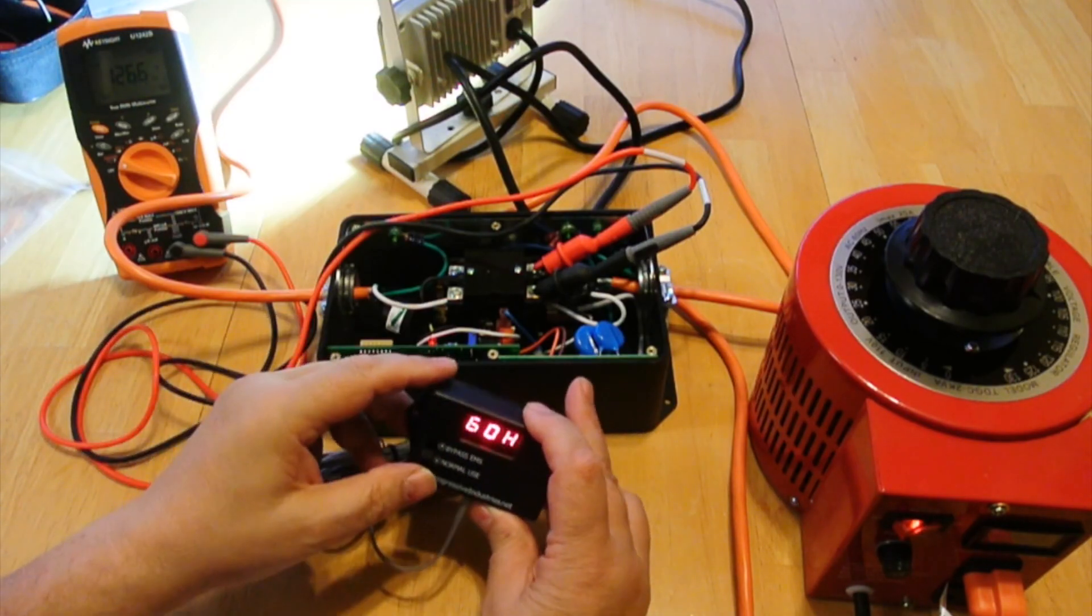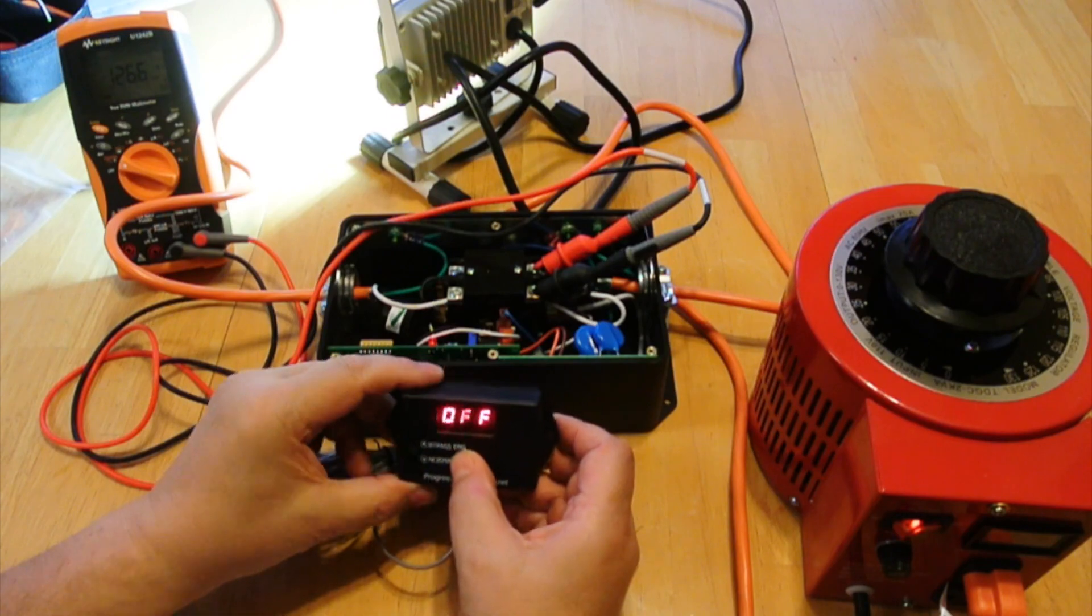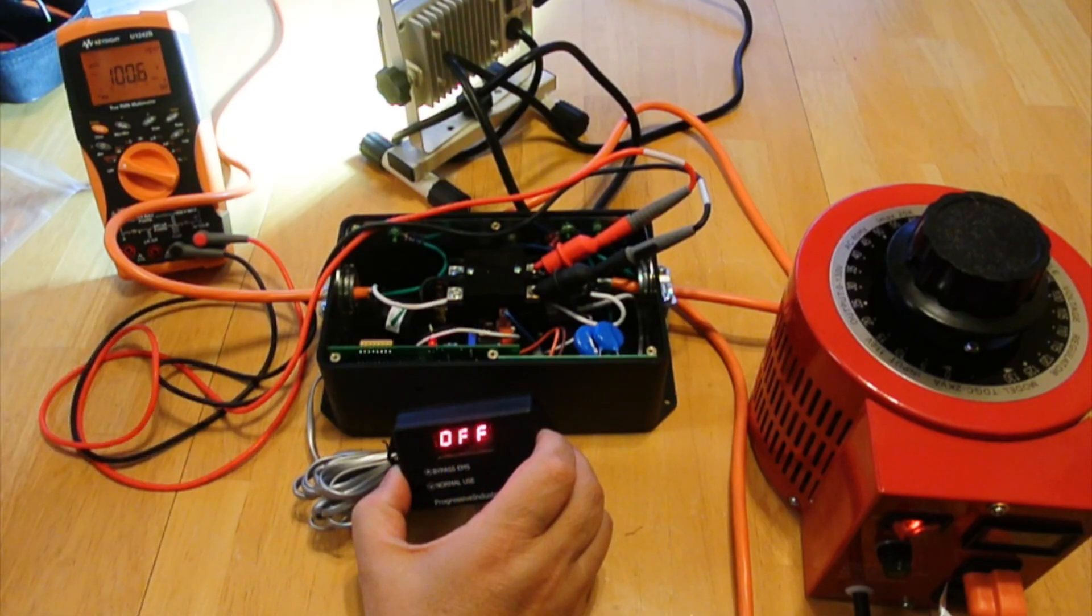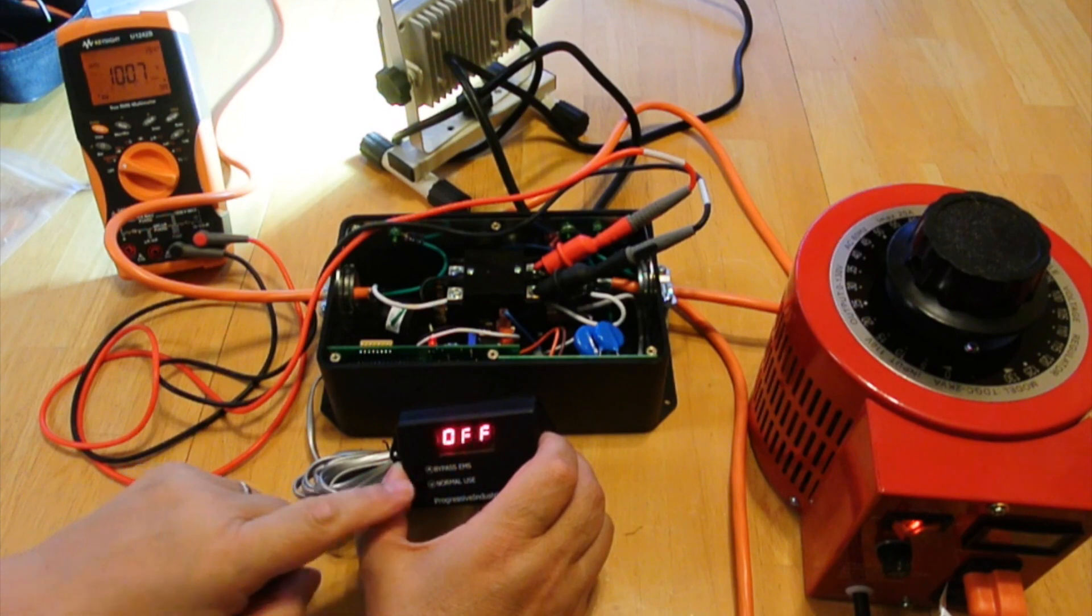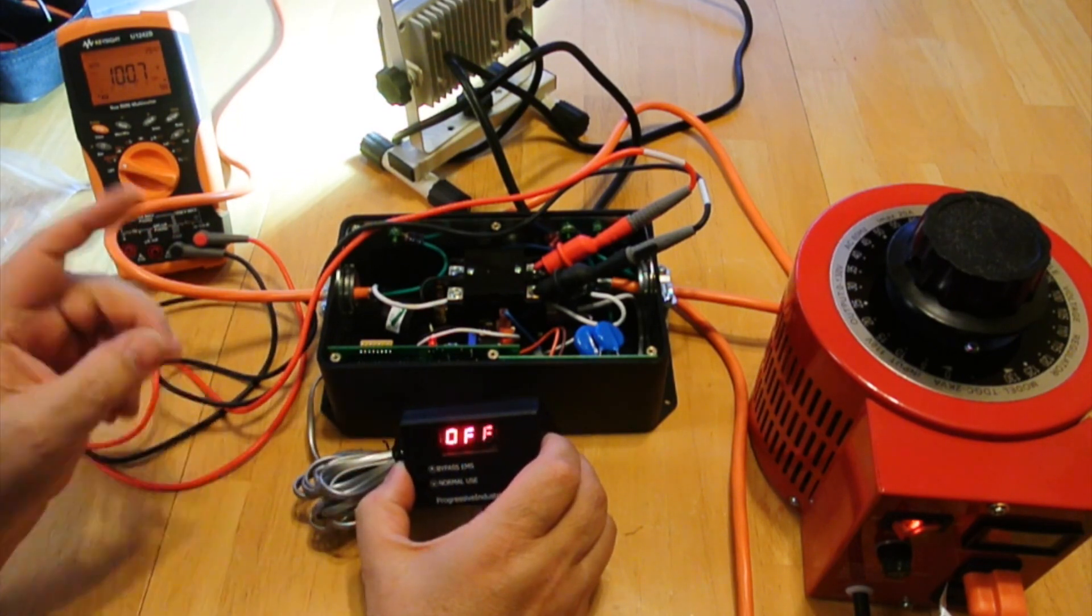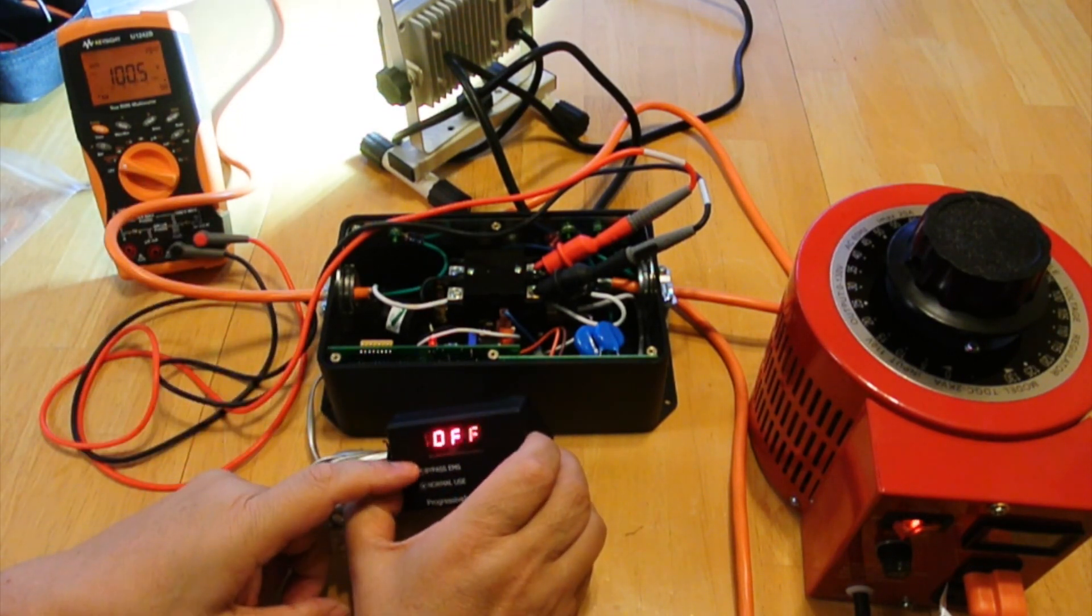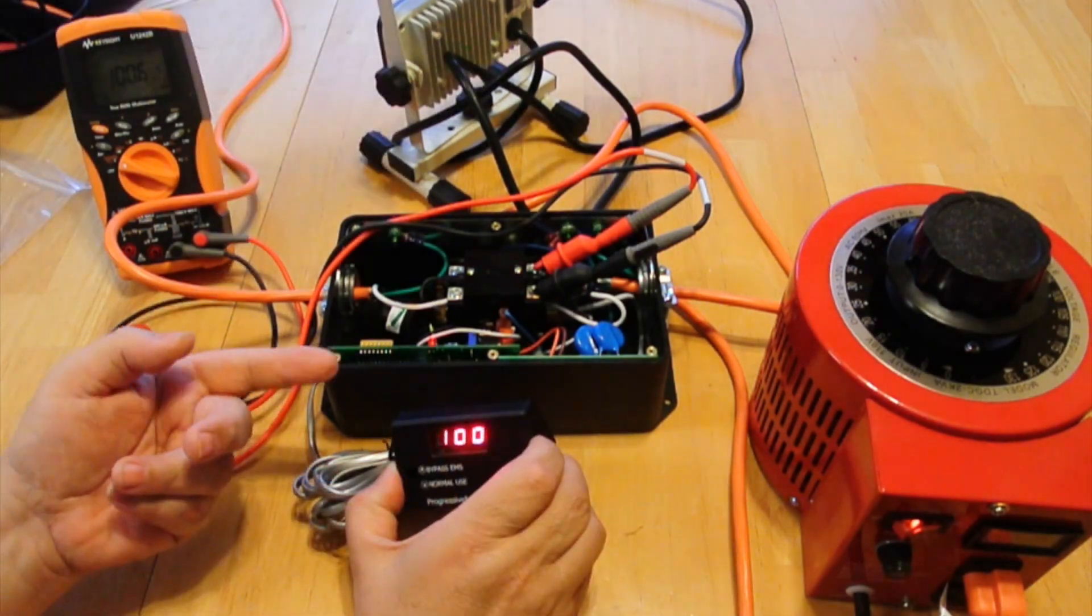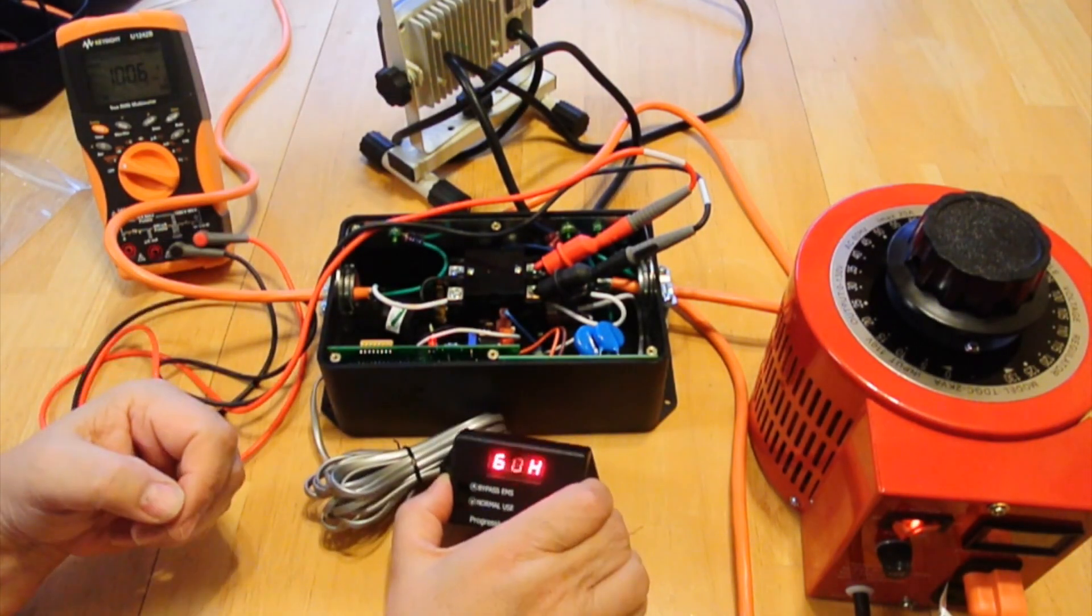Now, if we go into bypass mode, we turn it off. So if we go down to less than 104 volts with this off, you can see here the EMS system does not work. And if we turn it back to normal, now it's showing 100 volts and it worked immediately.